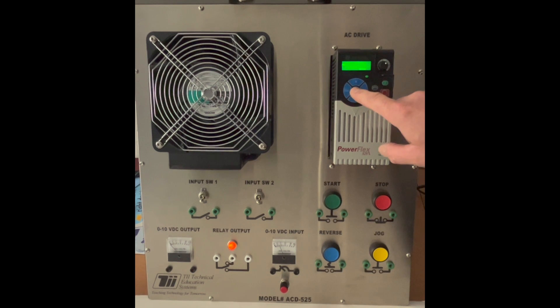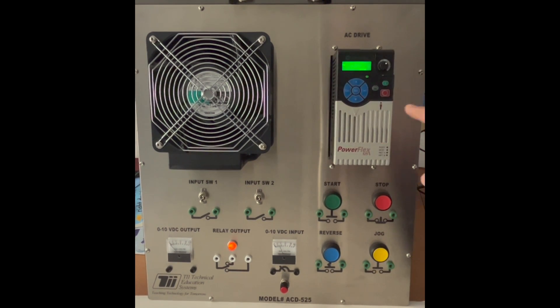But we want to change that so we're going to hit select and we're going to go up to 5. And I always recommend if you're doing this by hand to give it a second and it will walk you through and say this says 0 to 10 volts. Some can be used and set to 4 to 20 milliamps, 1 to 5 volts, whatever analog signal is required. But what we have coming in now is 0 to 10 volts. So we will enter that in.